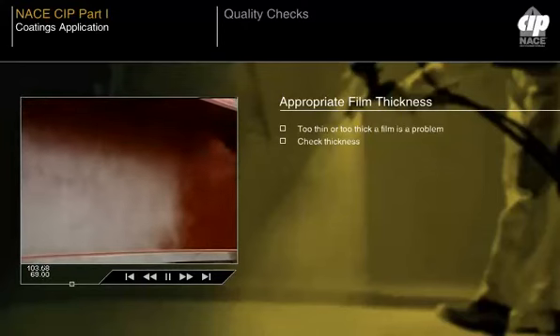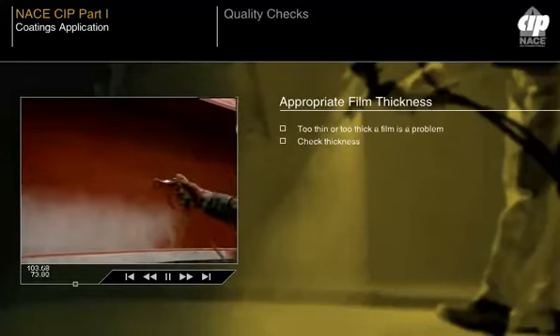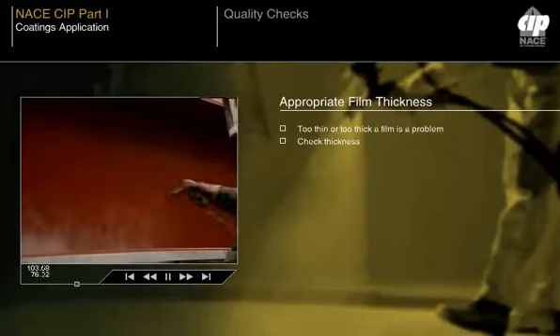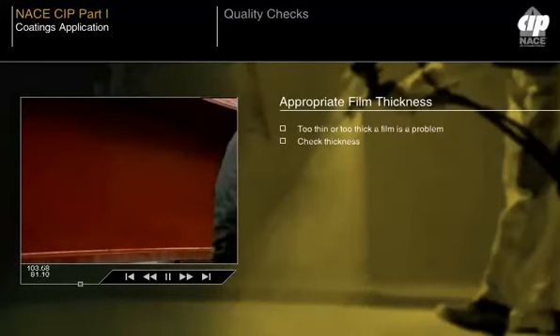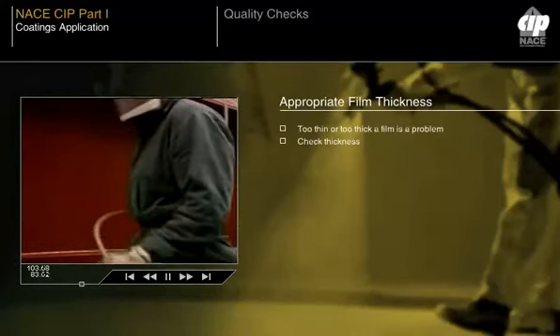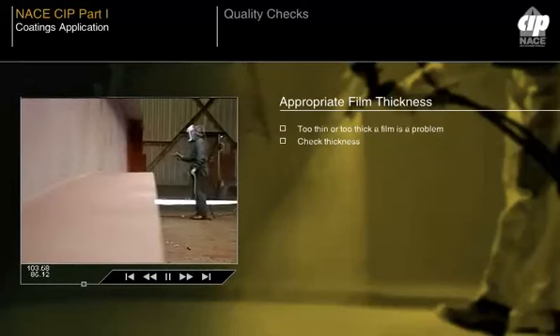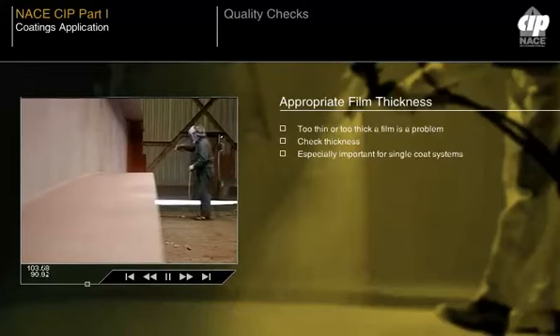Coating should be applied in an even, uniform film, allowing coating to wet the surface. Use thin, multiple passes with 50% overlapping to achieve a uniform film and ultimately the final proper thickness. Special care in application is needed for control of single coat systems. Errors in coating film thickness applied cannot easily be corrected, and it is important to get the application right first time.